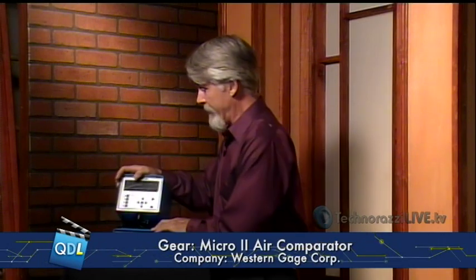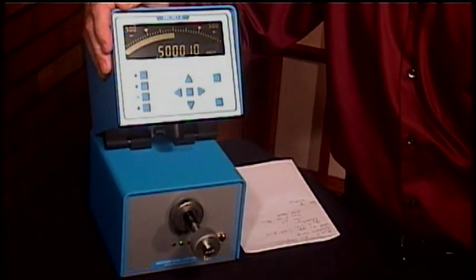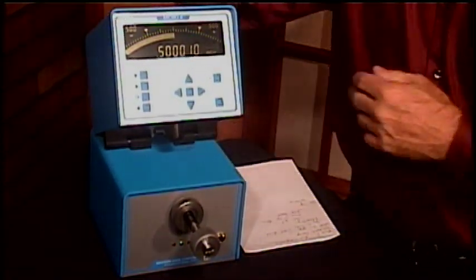Very quickly you can do go/no-go tests on parts and look at the variance of a part. This probe is set up for inside diameter, but you can also get probes for outside diameter, depth, and a number of other types of dimensional measurements. A couple of features of the Micro 2 from Western Gage that I really like are the ergonomic design — one is this tiltable head. Regardless of whether I'm sitting at a bench or standing, I've got a really nice view of the display. The display itself is one of the largest LCD displays for this type of device, so even standing two or three feet away — arm's length — this is very easy to read.